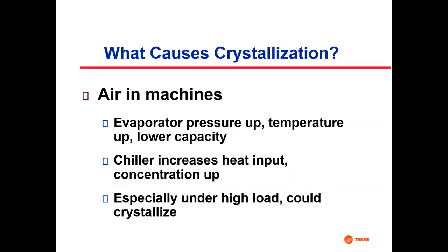One thing that can happen is air can leak. Remember the low pressures. The high pressure was like 0.135 PSIA, and atmospheric pressure is 14.7. So this is 11, 12 PSI vacuum, and that's on the high side. On the low side, it's 10 times less than that. So seals and all that sort of thing are critical to keep the air out.